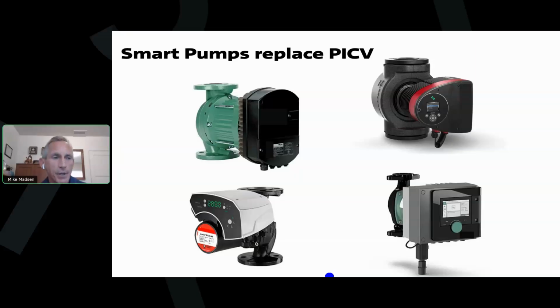No, it is. That's a national. That's also a Department of Energy requirement that every manufacturer uses a PEI, a pump efficiency index. And so we all rate our pumps. So it gives you a good benchmark, so you can compare brand A against brand B with this PEI value. The PEI value is set at specific flows that may not match a true load profile, but it does give you a good starting point, a good benchmark to compare two products against each other. Good question. That's all I got for questions.